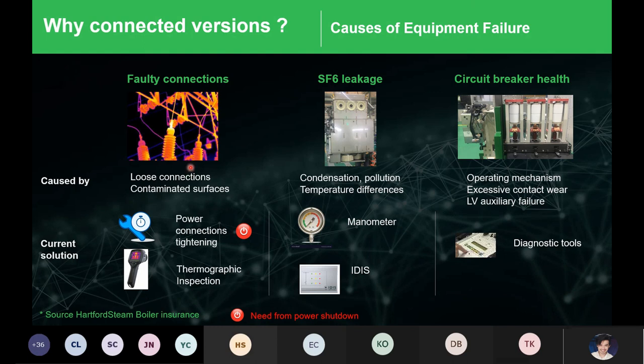Right. So there's a few ways to resolve this. One is that you tighten it on a regular basis, and also you use thermographic inspection tools to monitor all the hot joints. The second thing is that when we refer to switchgear, another concern is whether there is a leakage in the SF6 gas, because the SF6 is used for insulating the components inside. So a regular monitoring regime is needed for the manometers or the LEDs, which is called the IDIS, and also the circuit breaker health. All right, so after regular switching, or sometimes when the breakers are too old, the lifespan starts to degrade due to wear and tear. So you need certain diagnostic tools available to actually monitor the health of the circuit breaker.